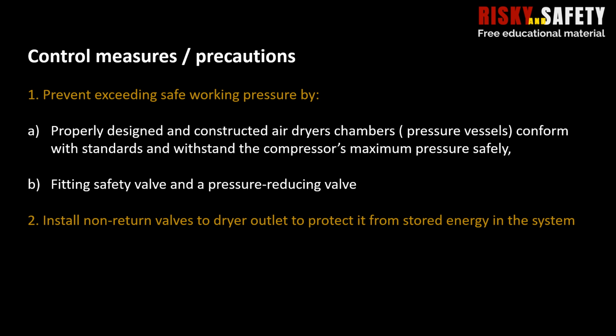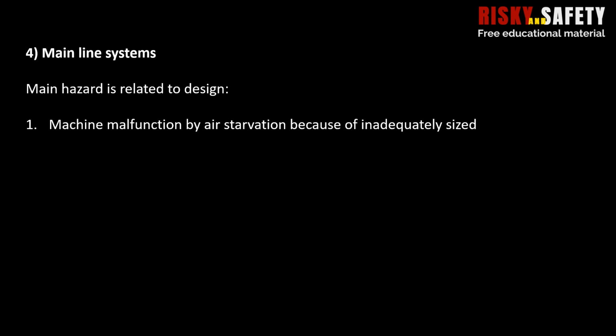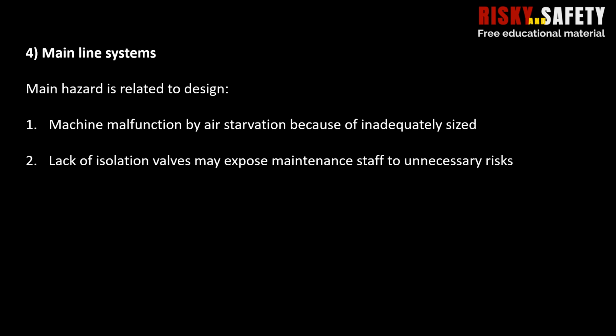Mainline systems. The main hazard is related to design, such as machine malfunction through air starvation because of inadequately sized and designed systems. Lack of isolation valves may expose maintenance staff to unnecessary risks, as may a poor choice of materials, so designers are advised to consult manufacturers when selecting materials.